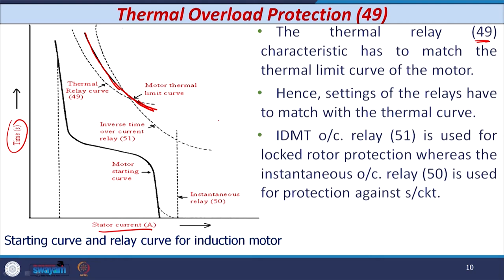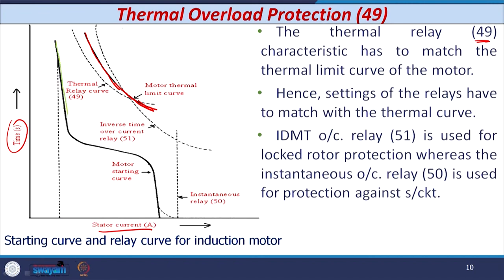The thermal relay curve (49 curve) is exactly below the motor thermal limit curve. Just below that is the motor starting curve. When you start the motor, the motor starting curve should be below the thermal relay curve specified by the manufacturer. Along with this, there are two more curves: an inverse time overcurrent relay (51) against short circuit in the induction motor, and an instantaneous relay (50). Both relays 50 and 51 are used for protection against short circuit. The relay 51 curve should always be separate from the motor thermal curve.